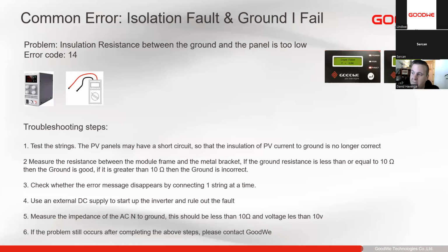But typically, if we get an isolation fault in the early mornings or anything like that, it is normally from the module side. So sometimes modules delaminate, or there's a slight cable damage under the modules. So when the humidity is high or there's dew, then we might have an isolation fault. So when there's more moisture, it's more likely to leak the current to ground. Then it's something on the modules or on the wiring to the modules that needs to be rectified.